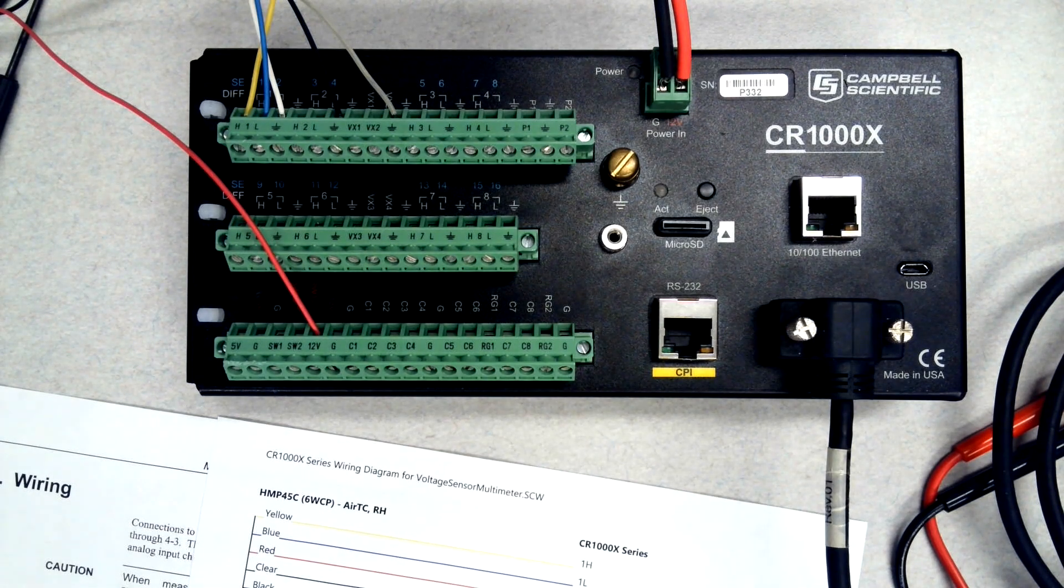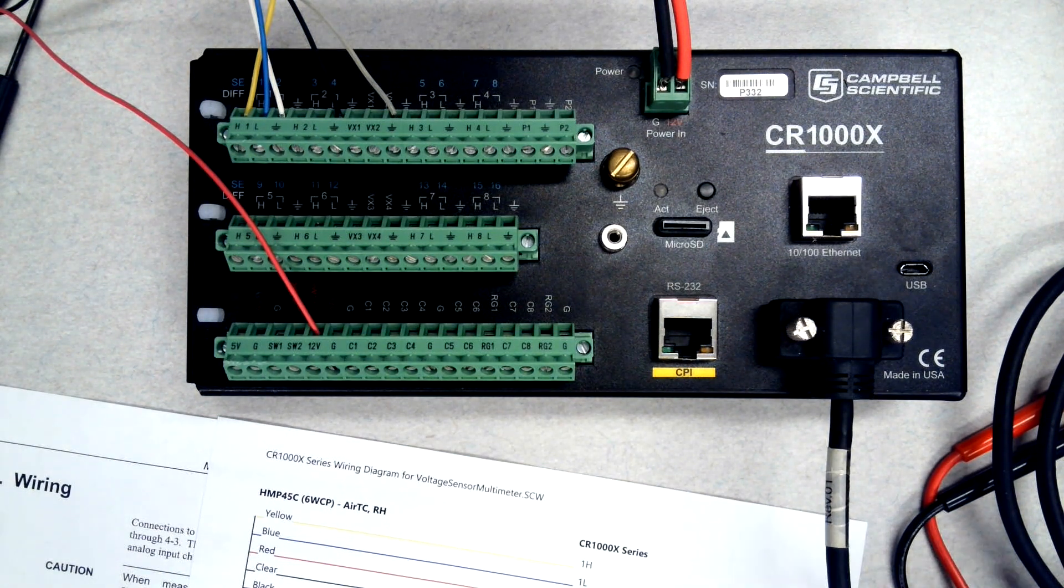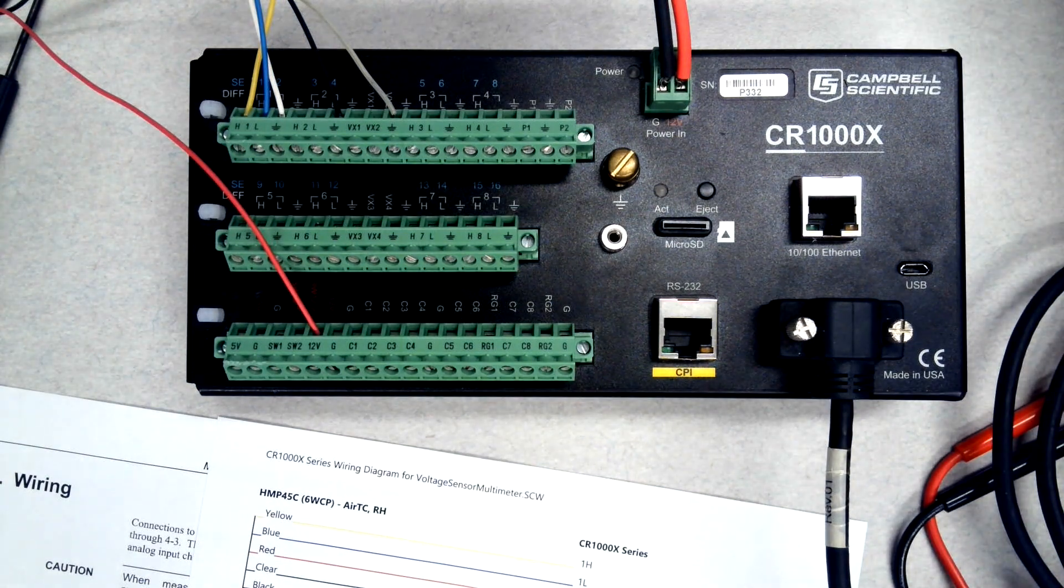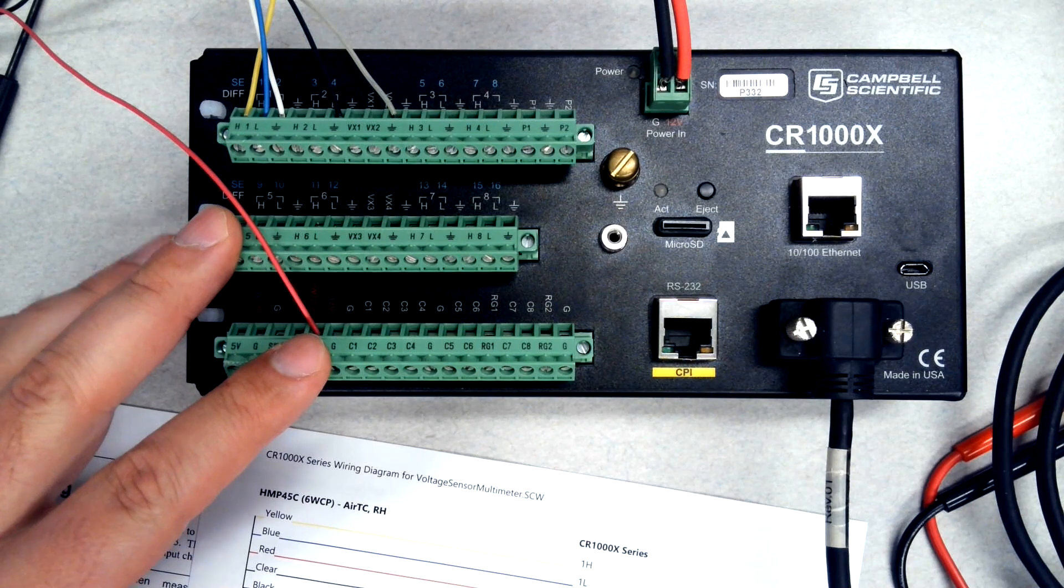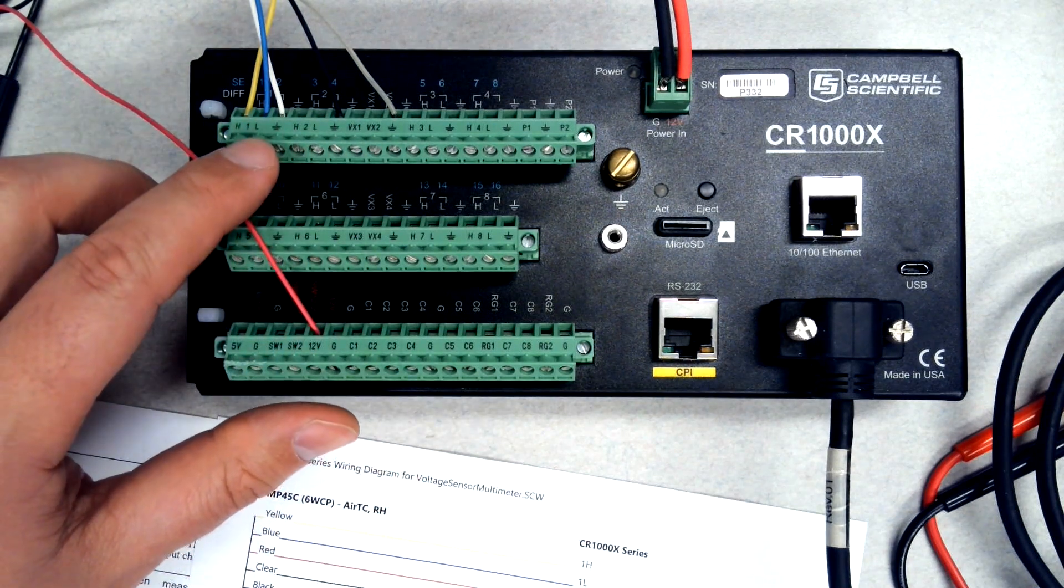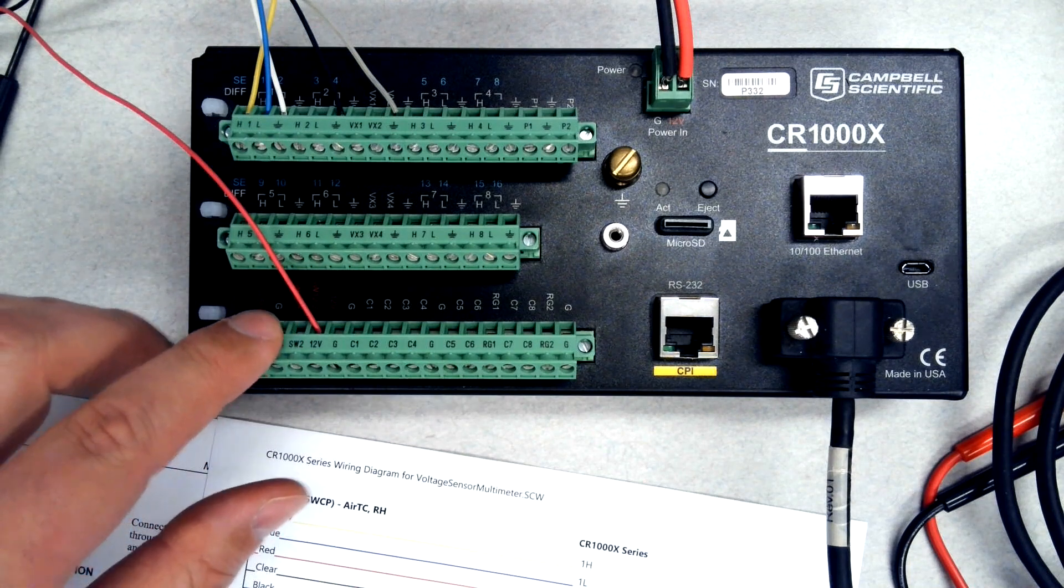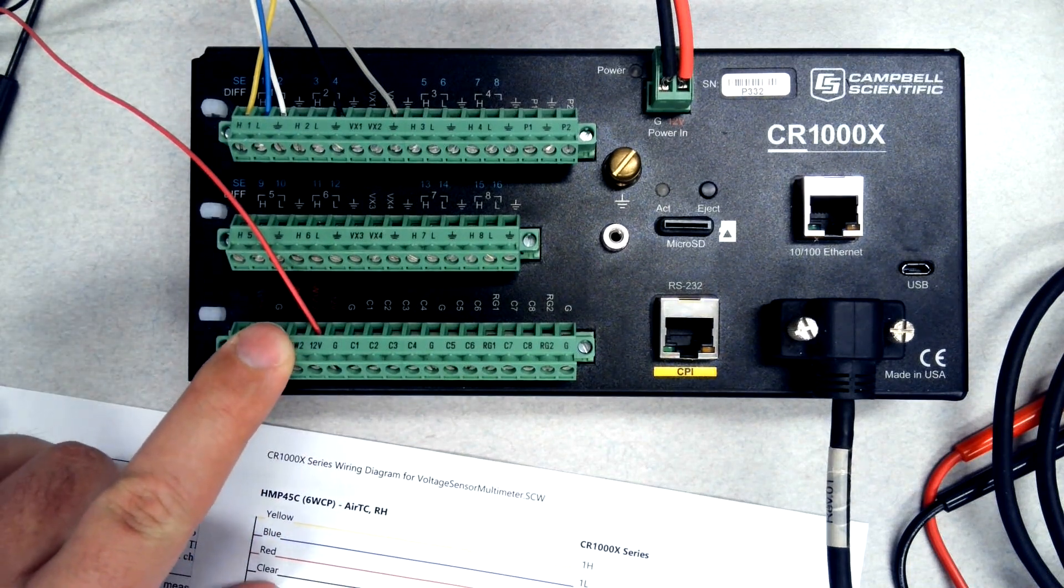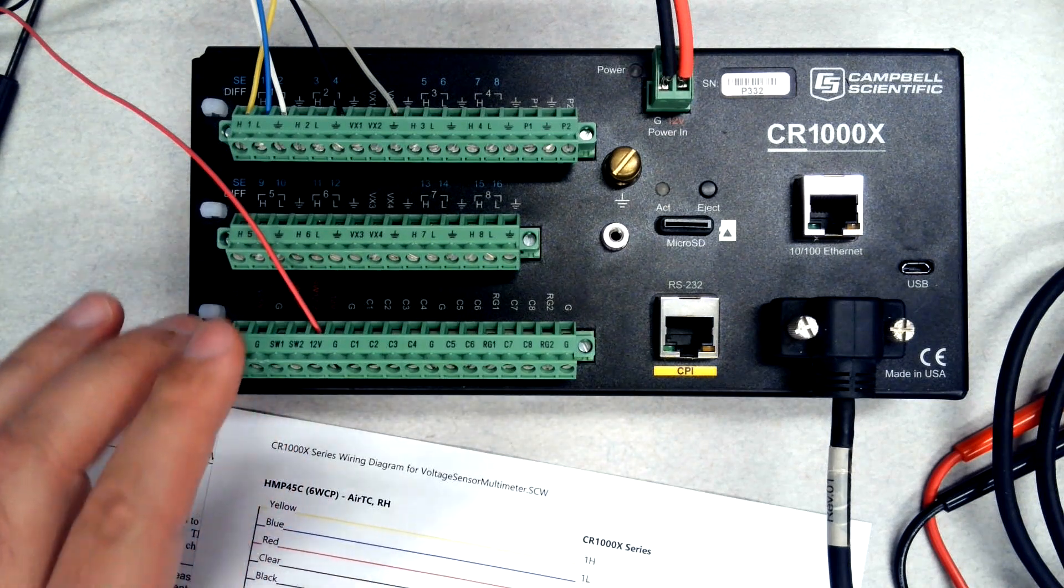This will be a demonstration of how to troubleshoot the measurement of a voltage output sensor. What we have here is a CR1000X data logger with a sensor connected that has two single-ended voltage outputs. This sensor also requires 12 volts power. Some sensors might be running off 5 volts or 3 volts.